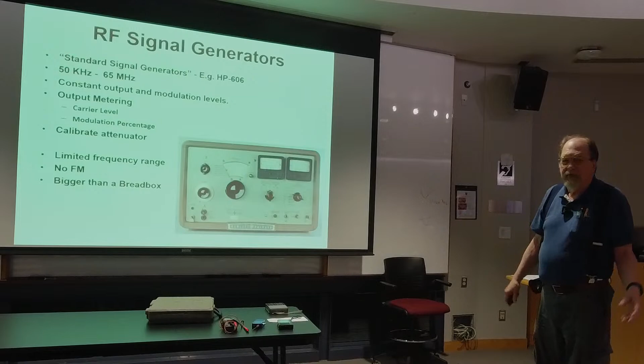Standard signal generator, one of the things they do is as you tune across the band, the output level remains constant. So if you wanted to do a frequency measurement across something, it would do that. Also, the modulation level remains constant. This is not the case with cheap instruments. So if you're down to actually making measurements, you know, I swear this receiver will hear down to 2 microvolts. Well, this is the kind of instrument you need to do that. Because the output meter more or less tells you the range of decibels, and then there is a calibrated attenuator, and you can go all the way down to like -90 dBm, which is a teeny tiny signal, and that's how those sensitivity measurements get made. Nice instrument, kind of big. It's tubes, so they're not too difficult to work on if necessary.